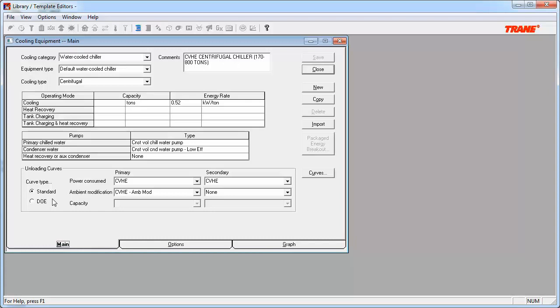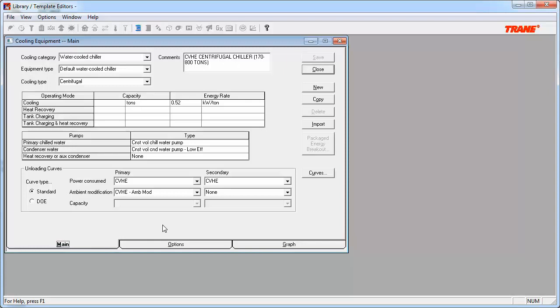Next, see there are primary and secondary curves. The primary curves describe how the equipment consumes energy in its primary mode of operation. For cooling equipment, that would mean cooling operation. The secondary curves describe how the equipment operates in other modes, such as heat recovery, tank charging, which could be looked at like ice making, and both tank charging and heat recovery.